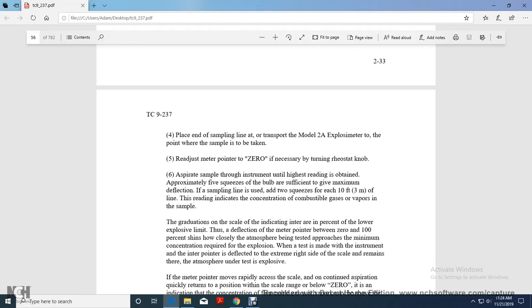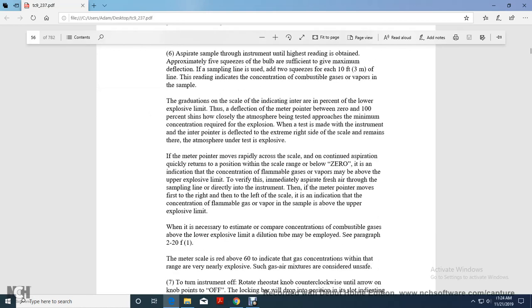Aspirate the sample through the instrument. The highest reading is obtained with approximately 5 squeezes of the bulb, which is sufficient to give the maximum deflection. If the sample is drawn through a sampling line, use 2 extra squeezes for each 10 feet of line. The reading indicates the concentration of combustible gases and vapors in the sample. The graduations of the scale indicate the percent of the lower explosive limit. Deflection of the meter pointer between 0 and 100% shows the atmosphere being tested is approaching the minimum concentration required for an explosion.